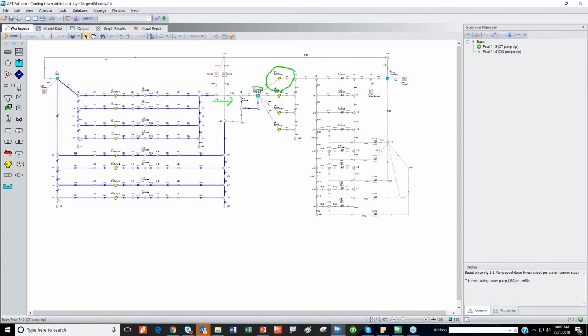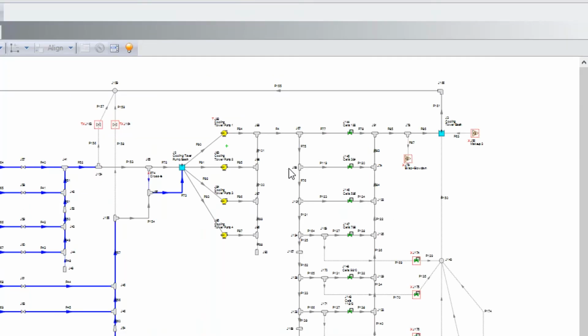So here we're going to simulate 2 cases. One case, we're going to stop a pump. We're going to trip a pump, one of the new pumps. The concern is that when we trip this pump, the flow continues going this way, so it can overflow this tank here. So what happens is the control protection system opens this valve to recirculate the water back to the basin. This is the protection system, and we want to check whether or not it's working.